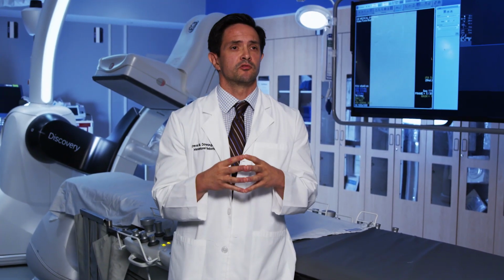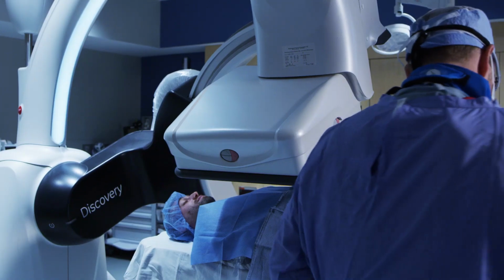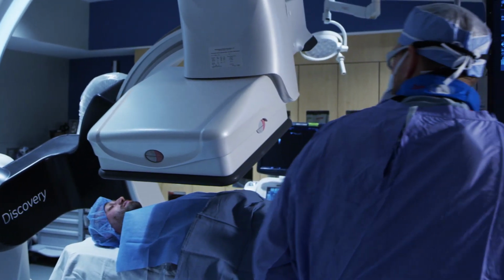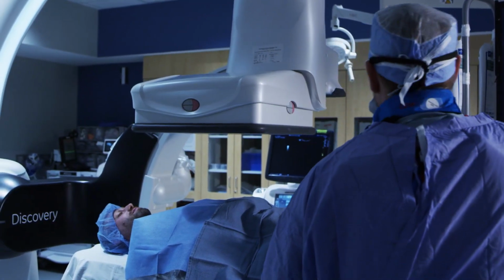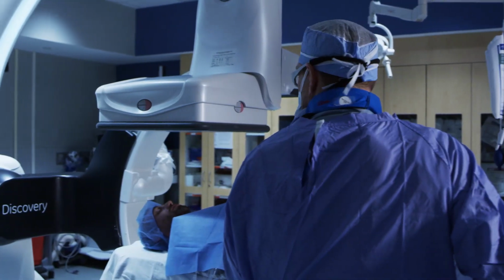When I was performing high-end procedures in other labs that we've used, the difficulty I had with rotational CT was a real constraint, in the sense that patients often had to be moved on the table, their arms raised up, in order to do these spins and make the machine complete the rotation around the patient. The requirement of getting a patient's arms above their head just to acquire a cone beam CT can be a major limitation. With the GE Discovery, I'm able to acquire cone beam images on almost every patient of almost any size with their arms down, with no repositioning.